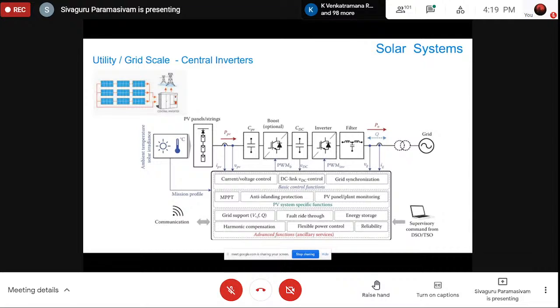And within the box, you can see a lot of control functions, which is grid synchronization, which I explained earlier, the DC link voltage, current and voltage control, because you need to control both the current and the voltage. There is one more function called MPPT, which is called maximum power point tracking. The subject itself is too big because MPPT itself is a very big topic.